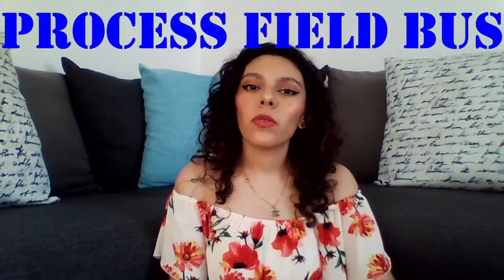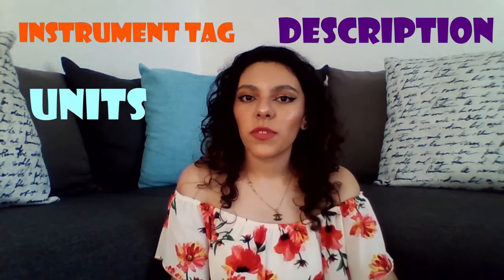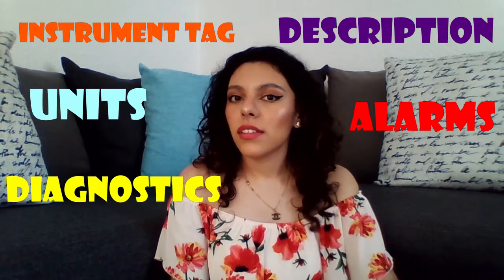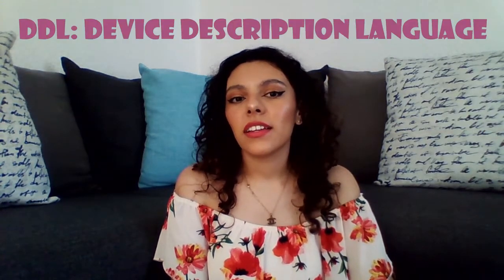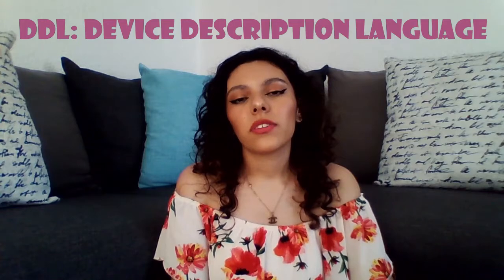PROFIBUS stands for Process Field Bus, and it is an open field digital network or field bus standard, which is responsible for communication between field sensors and the control system or controllers. It is suitable for both fast and sensitive applications and complex communication tasks. The instrument tag, units, description, alarms, diagnostics, etc., are supplied in files in DDL language, device description language. Something to note is that PROFIBUS is constantly evolving to be able to cover more and more needs thanks to the development of new features.